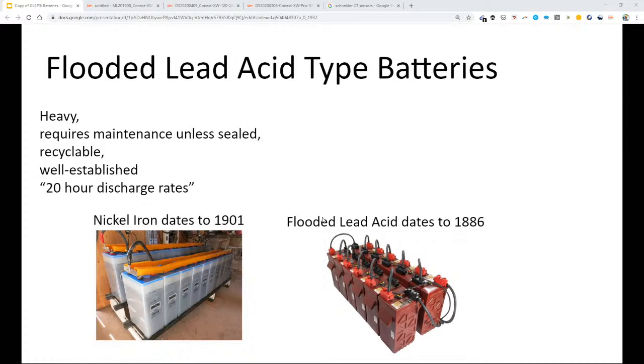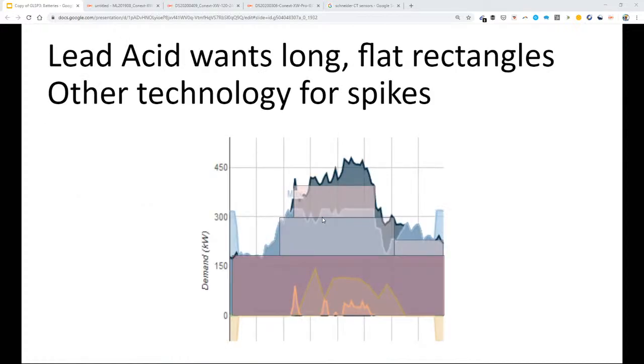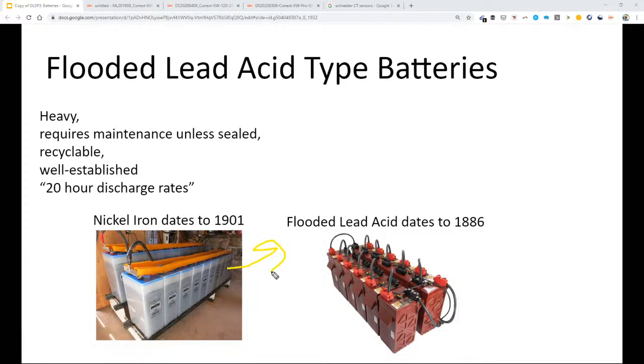Lead acid requires maintenance, it requires watering, and it has a 20-hour discharge rate, which means lead acid really wants an electric load that will drain the battery over the course of a day, not a load that jumps up and down throughout the day - where for 15 minutes it could discharge the battery over a course of 4 hours, but then for the rest of the time the battery isn't being used. When we talk about a 20-hour discharge rate, we're talking about the maximum load it's receiving, not the average load. It's as if it could be discharged at a constant load for 20 hours, not a variable load for 20 hours. A variable load would be a lot harder on a battery than a constant load.